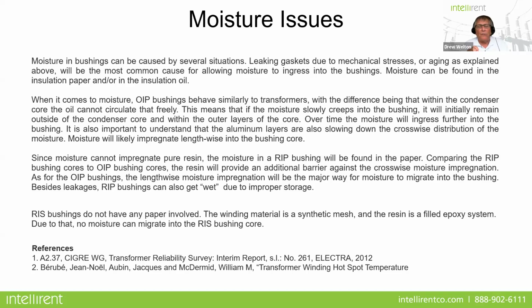So when it comes to moisture, your OIP bushings behave pretty similar to transformers, with the difference being that within that condenser core, the oil can't circulate that freely. When you have moisture in a transformer, it's constantly being circulated. And the amount of moisture in the oil versus what's in the solid insulation of the transformer depends greatly on the operating temperature.